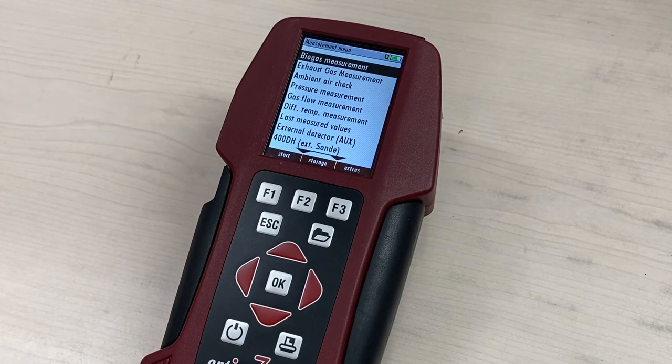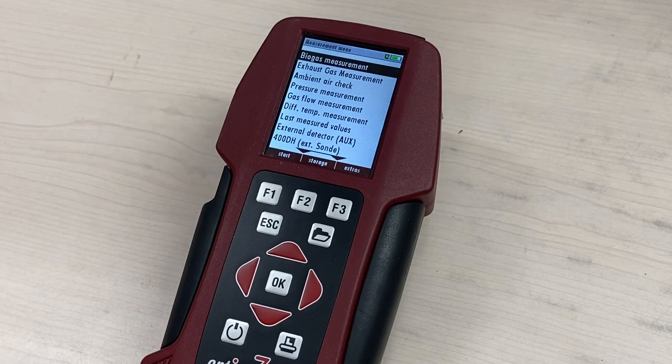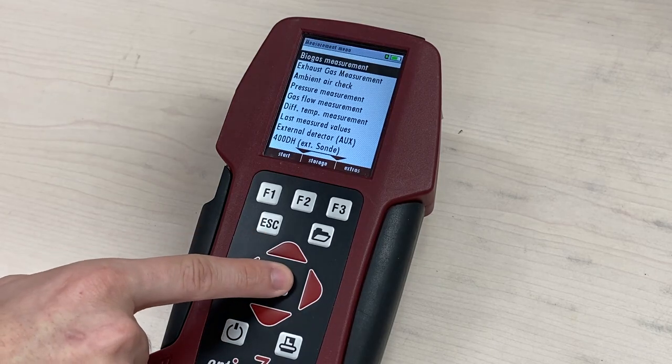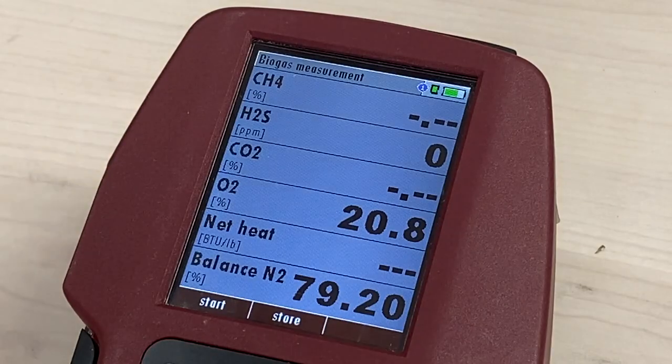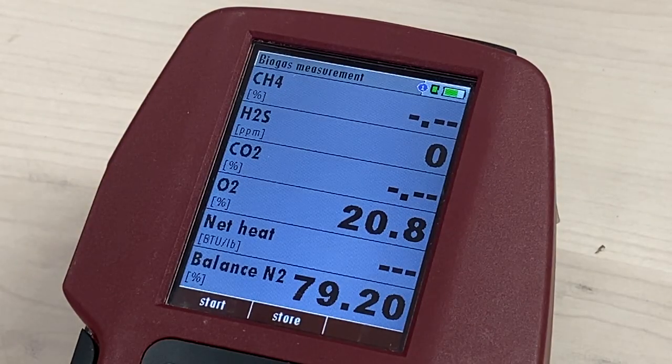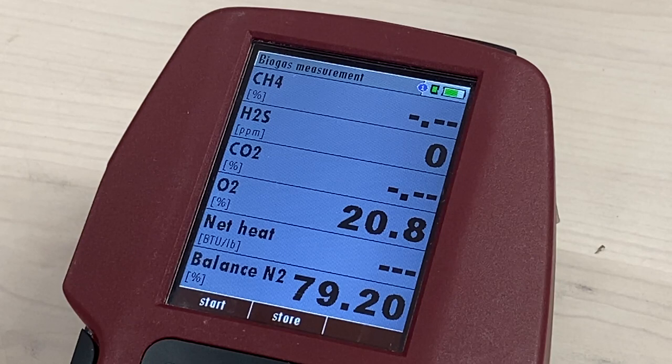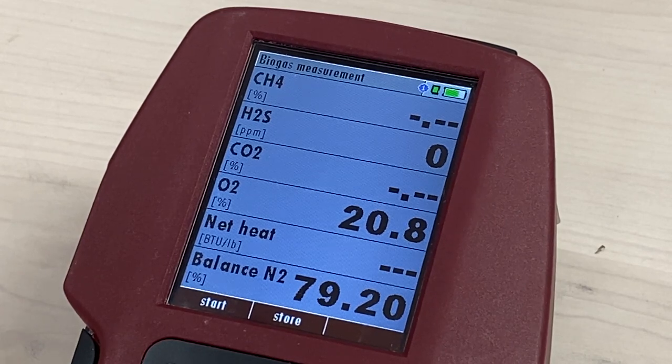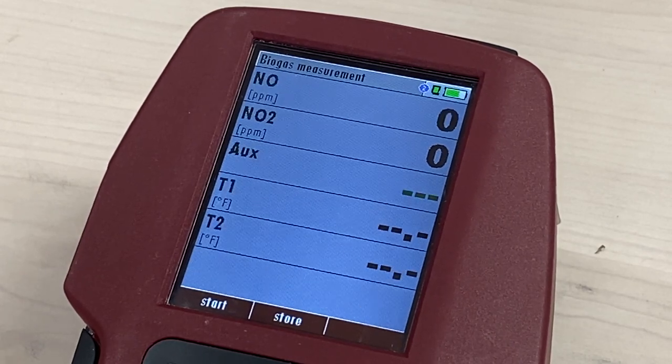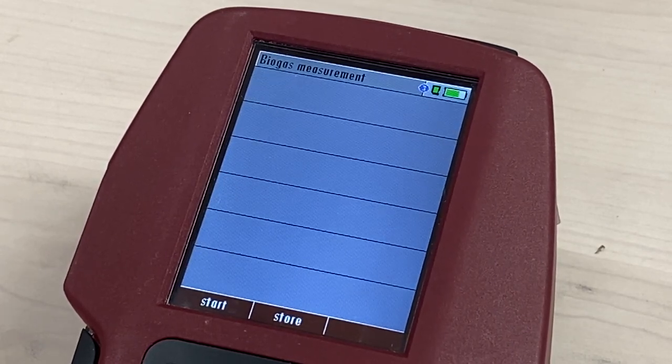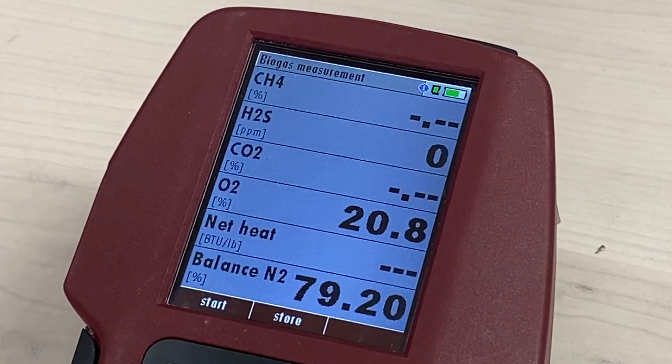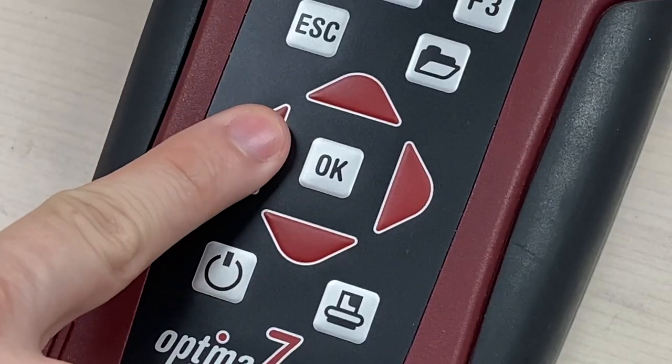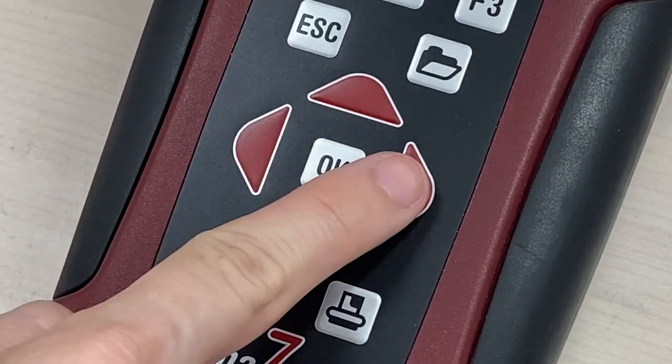There will be no alert that the new parameter was saved, but you can check by simply going back into the biogas measurement menu and checking. If you want to display a specific page from the biogas measurement menu, press the horizontal keys.